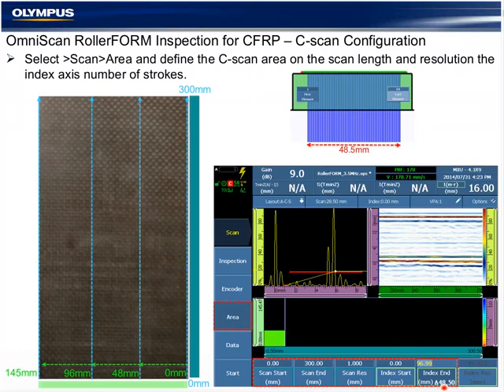So if I had a 0 here and a 0 here, the software would give me one stroke. It would be 0 to 48 millimeters for a single line acquisition, either on a time or the encoder. Every successive increment of this value is another stroke. So 96 millimeters here is telling the software I'm going to have stroke 1 at 0 millimeters. I'm going to hit my indexer button and take stroke 2, which would be 48 millimeters. And the last stroke, 3, would start at 96 and end at 145.